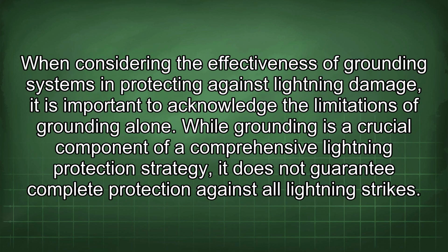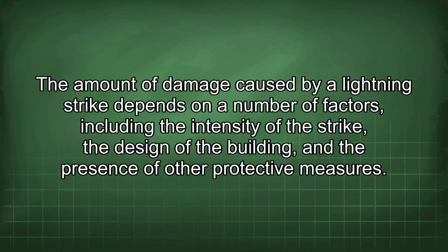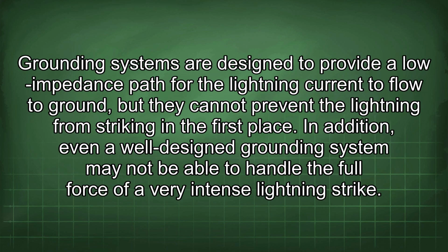When considering the effectiveness of grounding systems in protecting against lightning damage, it is important to acknowledge the limitations of grounding alone. While grounding is a crucial component of a comprehensive lightning protection strategy, it does not guarantee complete protection against all lightning strikes. The amount of damage caused by a lightning strike depends on a number of factors, including the intensity of the strike, the design of the building, and the presence of other protective measures. Grounding systems are designed to provide a low impedance path for the lightning current to flow to ground, but they cannot prevent the lightning from striking in the first place.